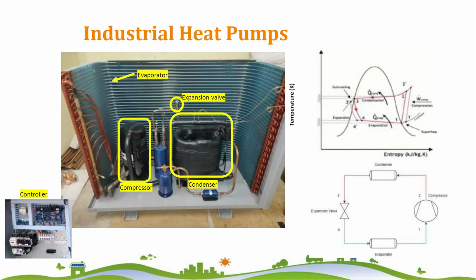Since a lot of companies are trying to adopt energy efficiency in their process applications, the heat pump is one of the best energy efficient solutions available in the market. The working principle of a heat pump is similar to any air conditioner or chiller. It works on the principle of the vapor compression cycle. Depending on the utilization point, the terminology of the system differs. If your utilization point is the evaporator, then it's called a chiller or an air conditioner. If your utilization point is the condenser, then it's called a heat pump. The name itself suggests that it pumps heat from lower energy to higher energy.